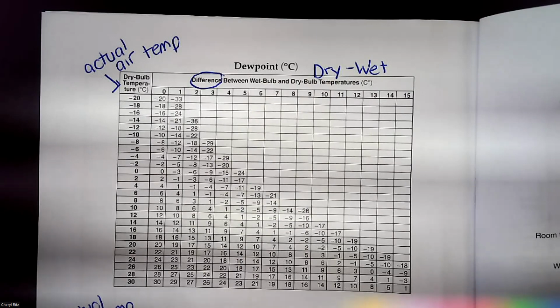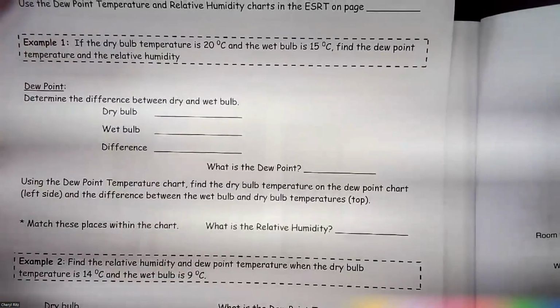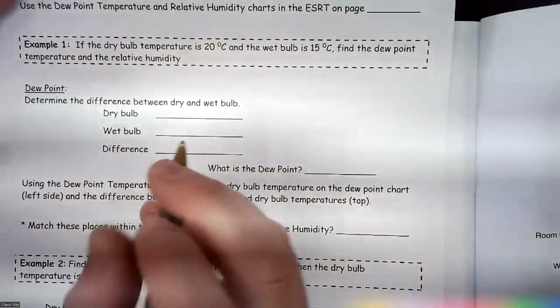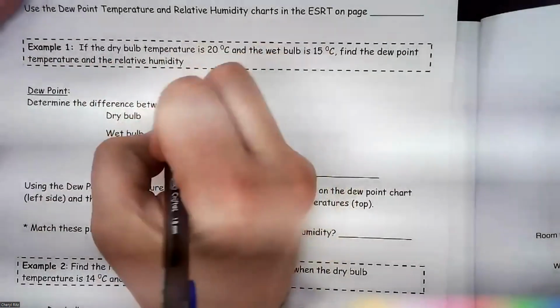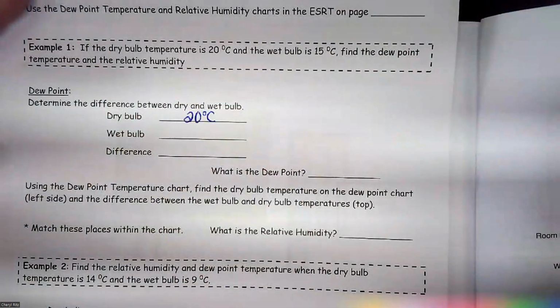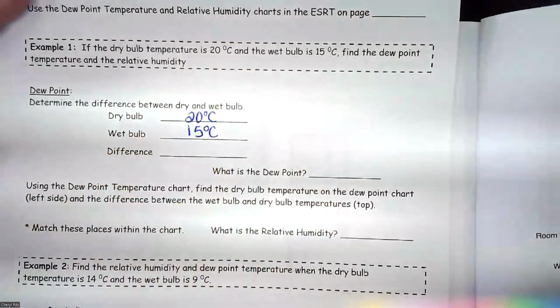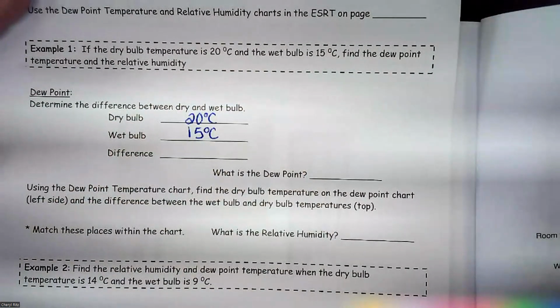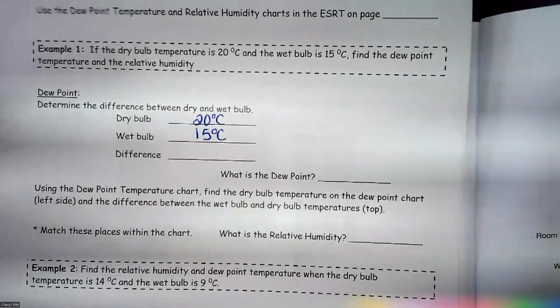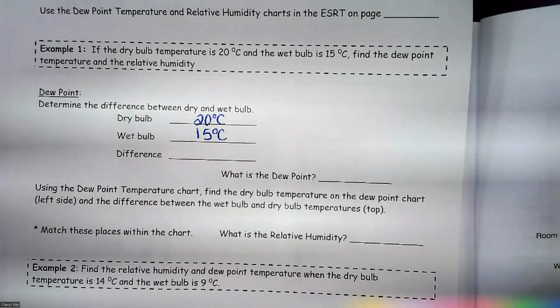So let's try this one out. We have example 1 here. If the dry bulb temperature is 20, I'm going to fill that in. Dry bulb temperature, 20 degrees Celsius. And the wet bulb is 15 degrees Celsius. Find the dew point and the relative humidity. So what's the first thing I should do? Let's find the difference. Now, I'm going to tell you guys, if you even question whether you're subtracting correctly, get a calculator and use a calculator.